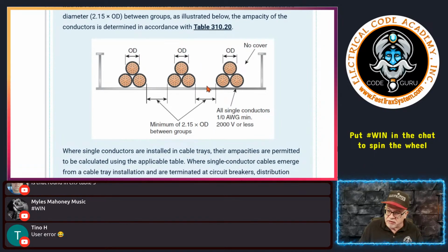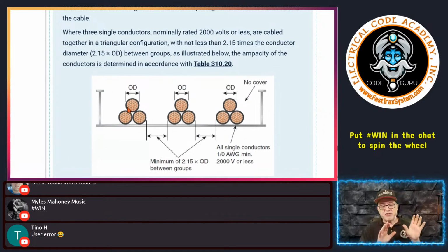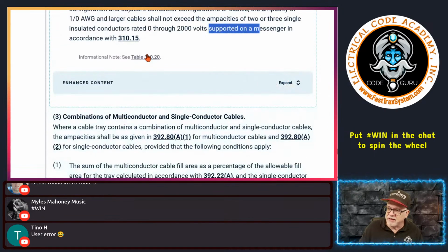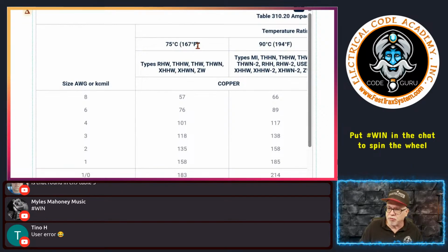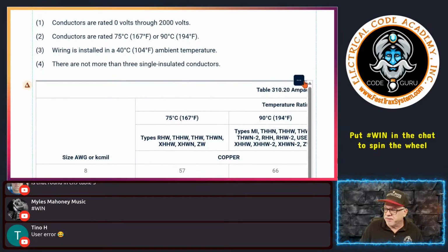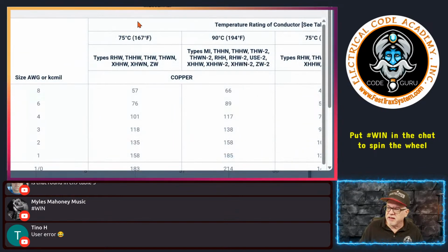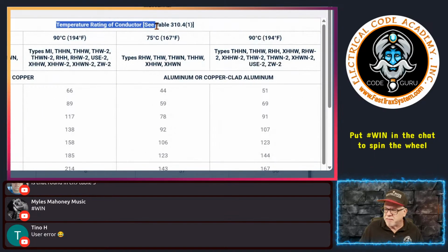And then you have the same space between that and the next one. You with me? So this could be a configuration that's running in a tray, and you're basically spacing them out, okay? If that's the case, and you do this, then you get to use the ampacities, and I'll show you something in this table. This table right here is ampacity of conductors. You can't see it because it's too low. But basically, this is ampacities, and it sucks.